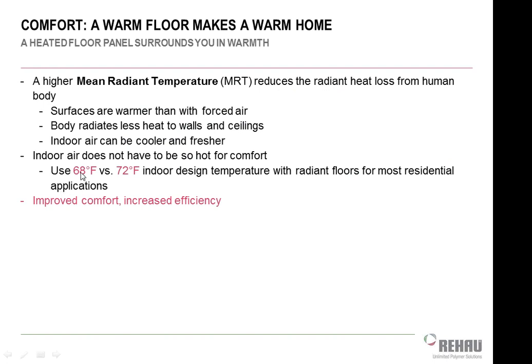Like we said, because of that, it's very common to see folks that have radiant heating in their building or in their home keep a lower thermostat temperature than they otherwise would. We do a lot of classes here in the office for contractors and engineers, and we always poll people when we talk about radiant systems, to see who has a radiant system in their house and what they keep their stat at. It seems like most folks here in the Chicago area, contractors and so forth, that have something in their own house typically have their thermostat set between 64 and 66 degrees with a radiant floor system.